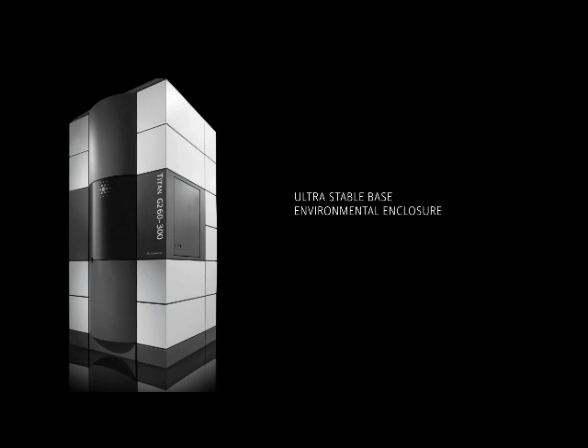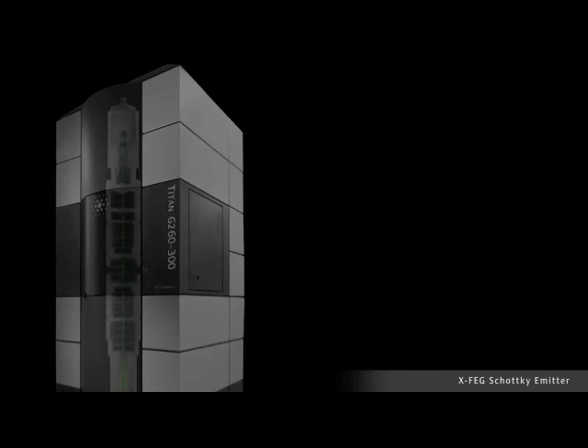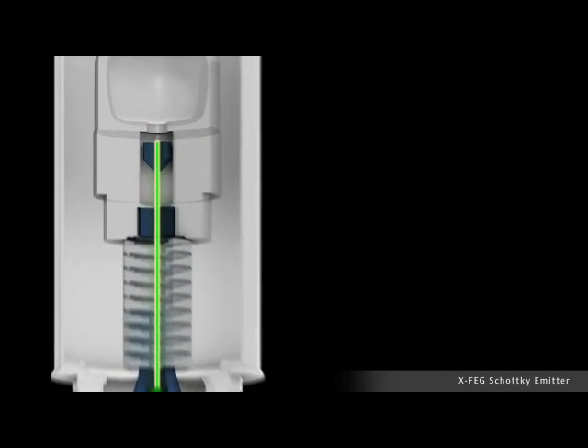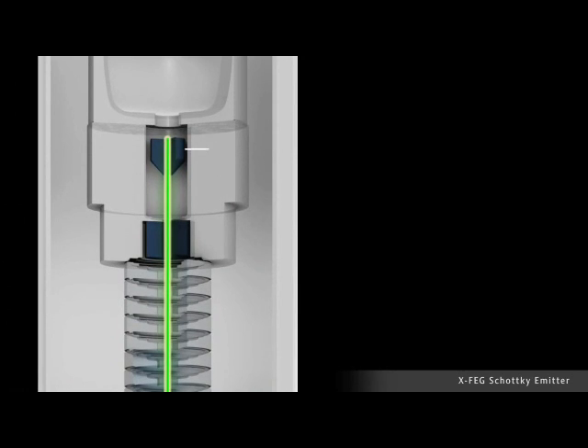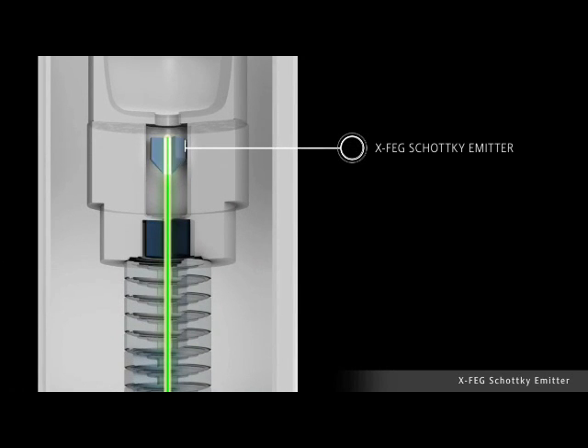Titan features an ultra-stable base with an environmental enclosure that effectively isolates the column from external interferences and maintains constant environmental conditions for exceptional performance. At the top of the Titan column is the highly stable, reliable, high-brightness electron source, the XFEG Schottky emitter.